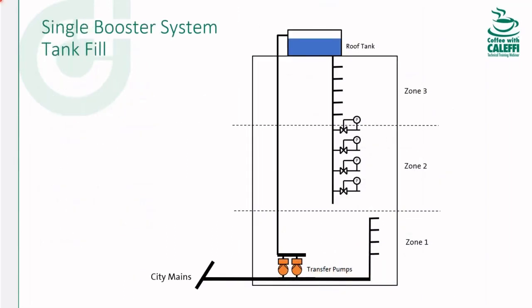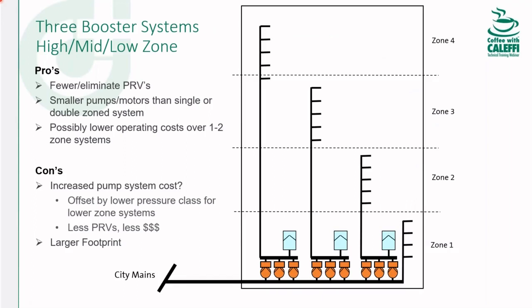And then again, a three tiered system has three pump sets there, so the installation cost gets much more, because you've got more riser pipes, you've got more pumps in the mechanical room, and you need all that space and things like that. So you just have to weigh in and assess everything. Right, nine pumps. Some people want to cut down the number of pieces of equipment. So nine pumps can be a little, I don't know, overbearing maybe.